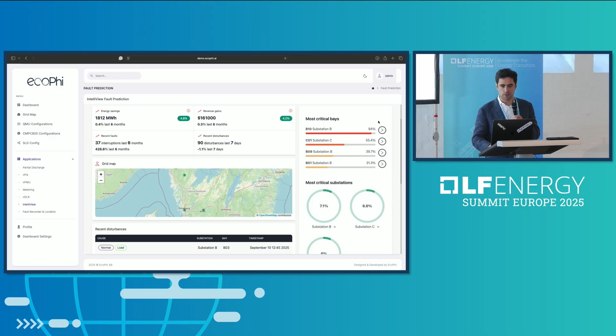And from that, you can also drive fault prediction, as I mentioned. For example, our sister company uses the data that we provide to predict the failures, down to the root cause. For example, we say this is a timeline you see in this particular feeder, that there is going to be a failure in the transformer. With explainable AI, anything that we predict will say why we are predicting such a high value. With the location, for example, this one is happening because of insulation degradation, 2.4 kilometers away. With the meter accuracy, we can predict where the failures are going to happen, and that helps to reduce the SAIDI. So this is basically an overall summary of the software.